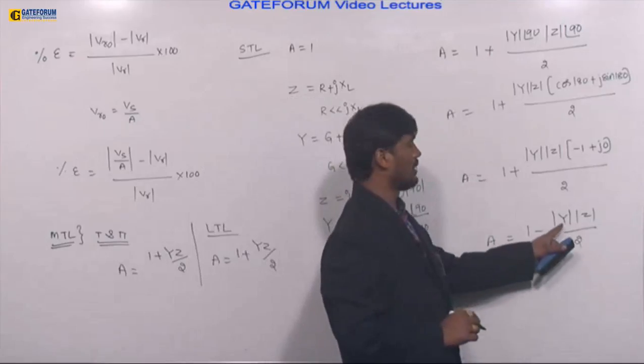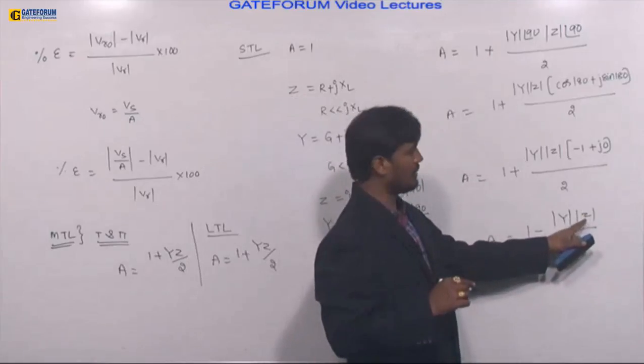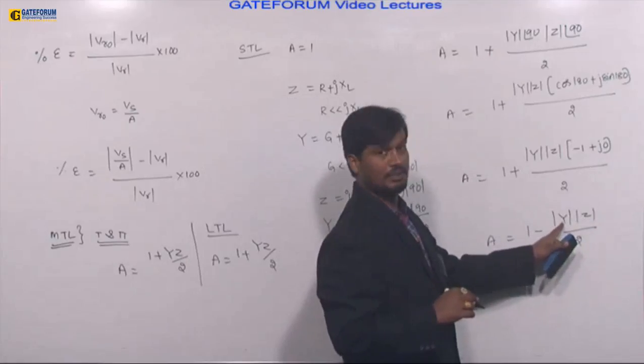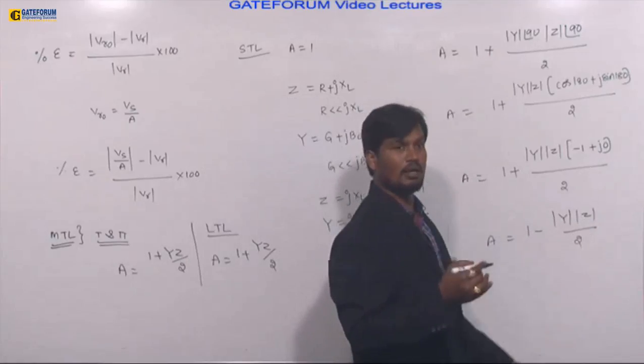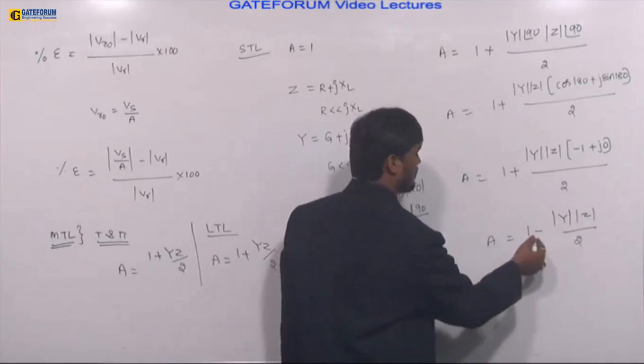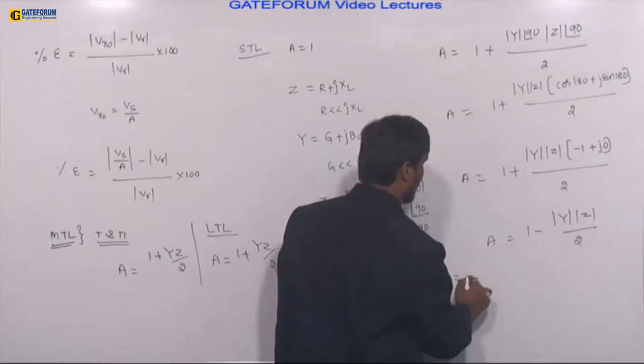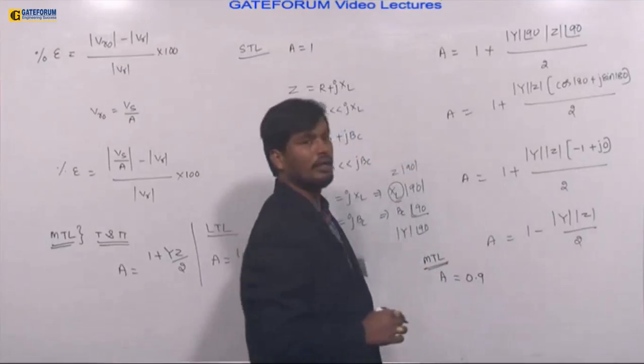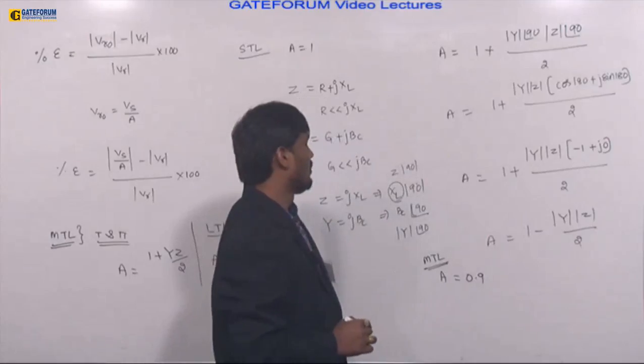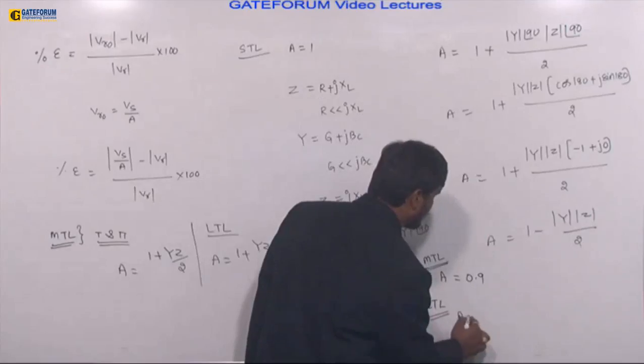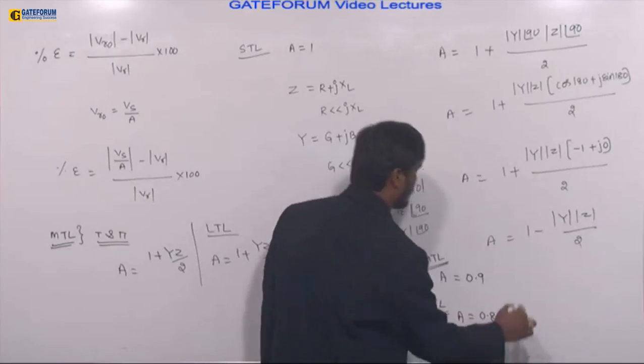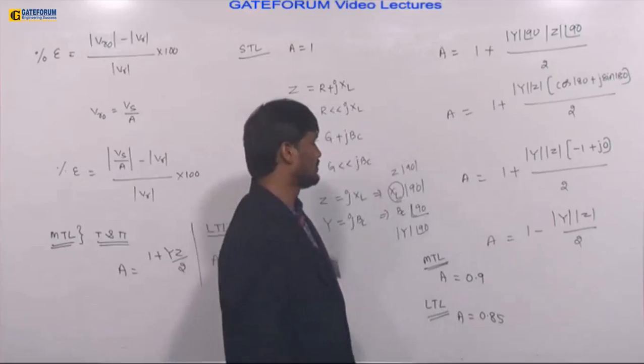For medium transmission lines, impedance (inductance) and admittance (capacitance) are less compared to long lines. As these values are less, YZ is less, and 1 minus a small value means A is closer to 1. A becomes 0.9 for medium lines, and for long transmission lines, A becomes 0.85.